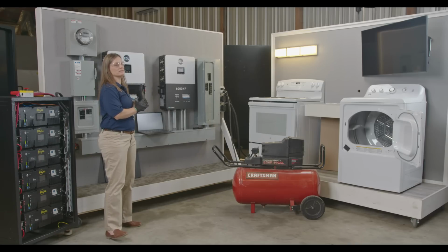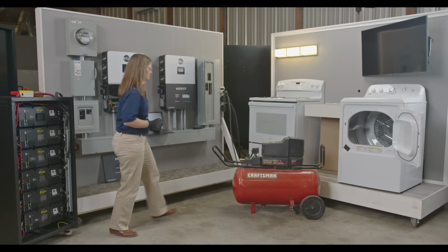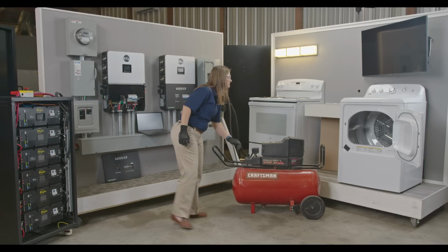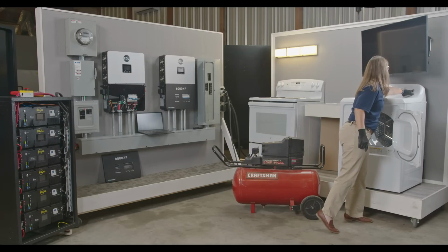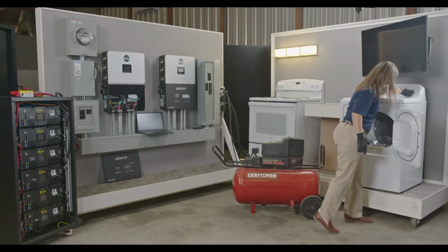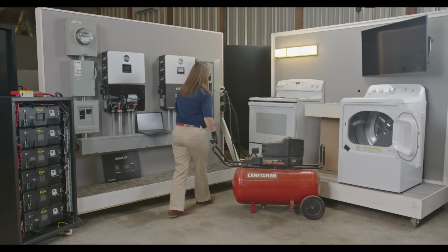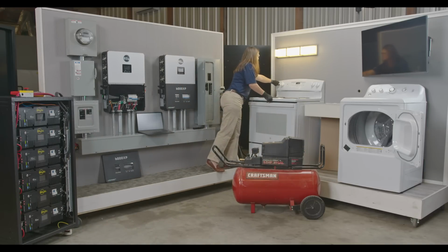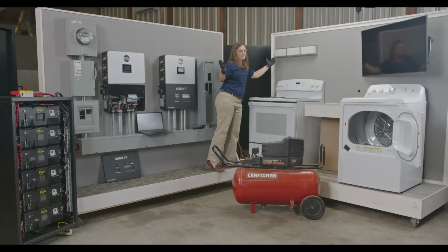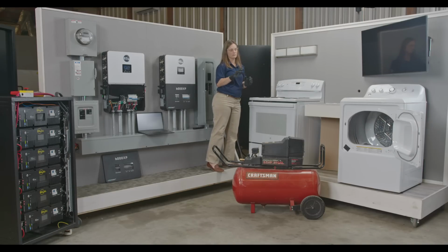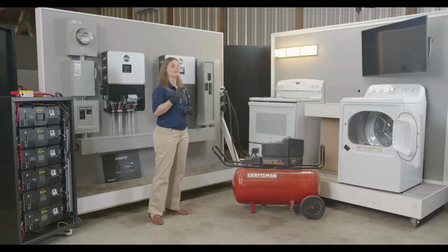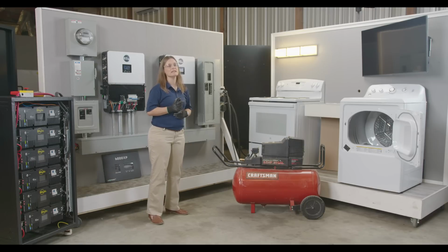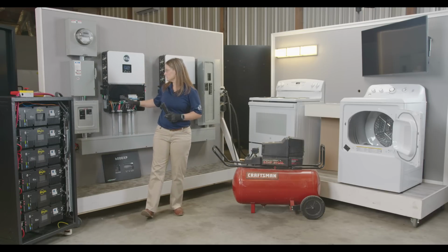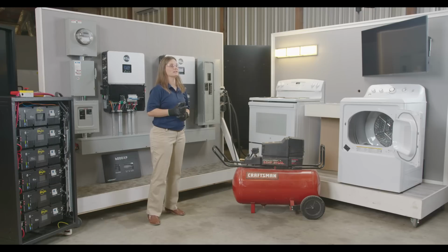Let's see if we can overload this inverter and make it turn off. We'll start with the compressor. And we got one burner on before it turned off, with the compressor and the dryer running as well as the light. Pretty cool. These inverters also have rapid shutdown capability with an external initiator wired to your ports right in here. Let's test them out and see if rapid shutdown works.